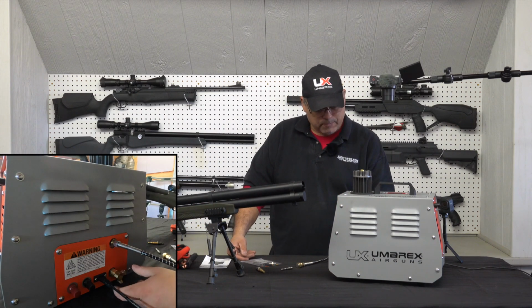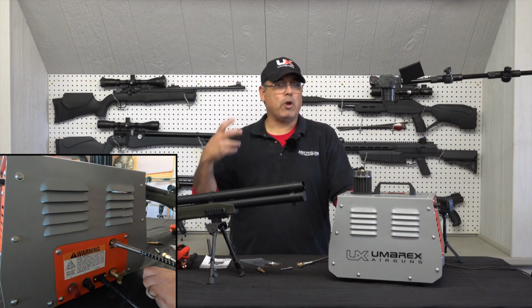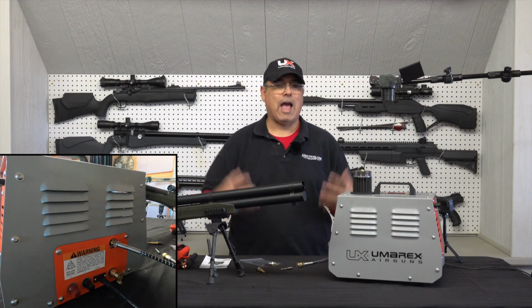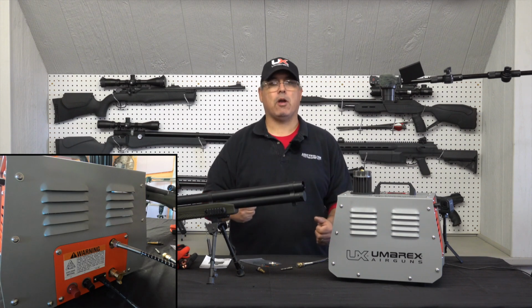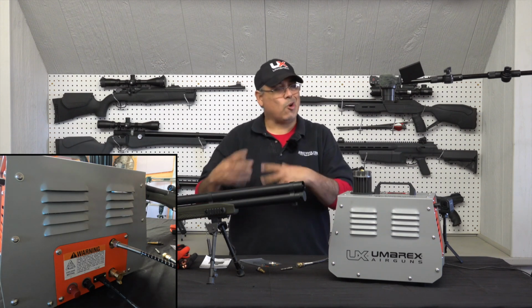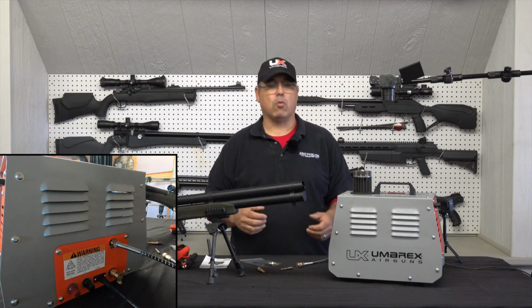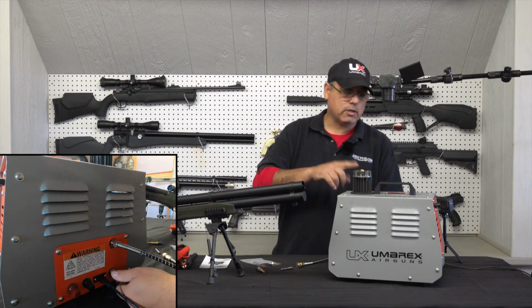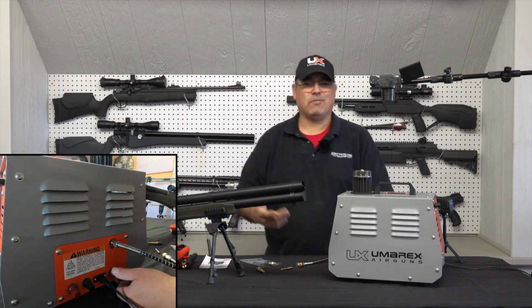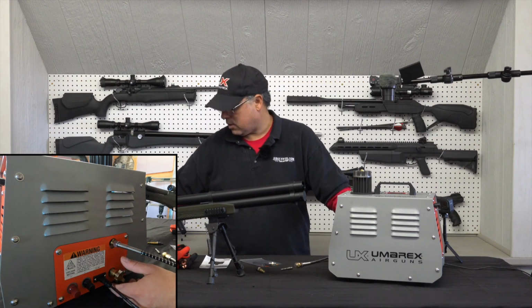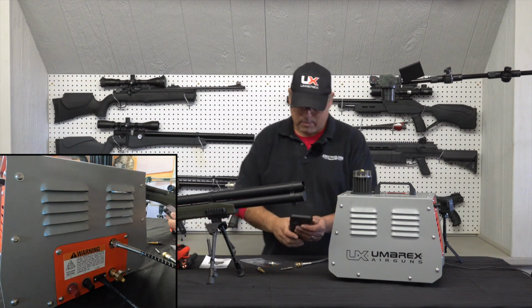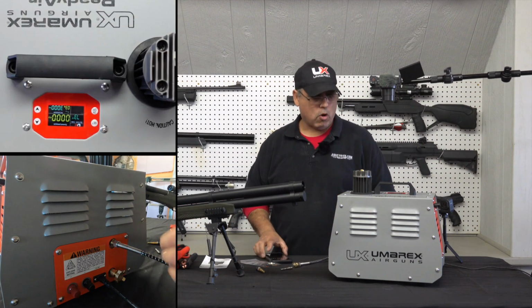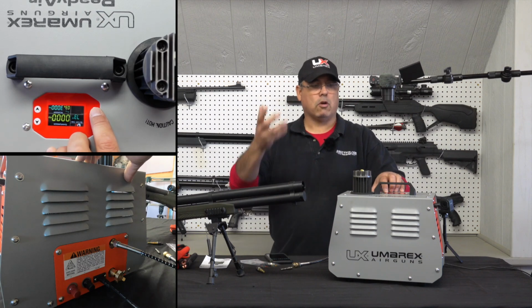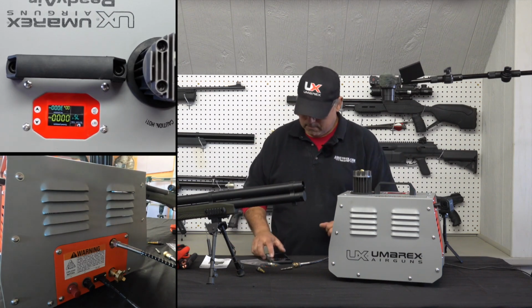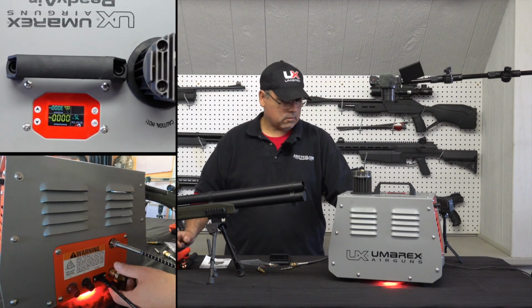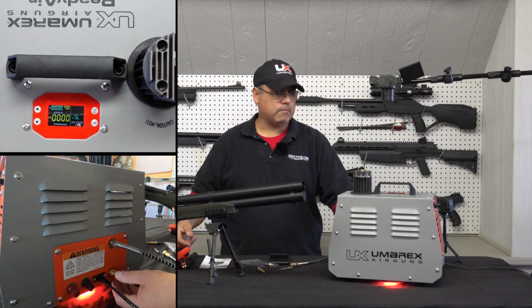The thing we want to make sure of is to always have the bleeder open when you start. You don't want the compressor having to make pressure the minute you fire it up. Give it a little time to start running, then close the bleeder and let it go to work. Let's go ahead and do this. Now watch the temperature, because that's going to go up. I don't know how long it'll take, so let's time it. All right, I've got the bleeder open, I'm going to hit the on button, and it's going to start to fill. Now I'm going to close the bleeder.